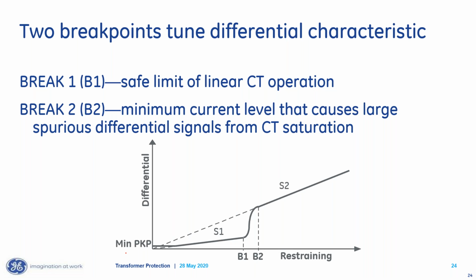As I said earlier, the challenge on differential is not getting the thing to operate for a true differential. The challenge is to keep it from operating for a legitimate fault. So for that reason, I like to set things more conservative. I'll set that lower break point at 2. And typically, my recommendation is to set that lower break point at 2, regardless of whether you've done the calculations or not.